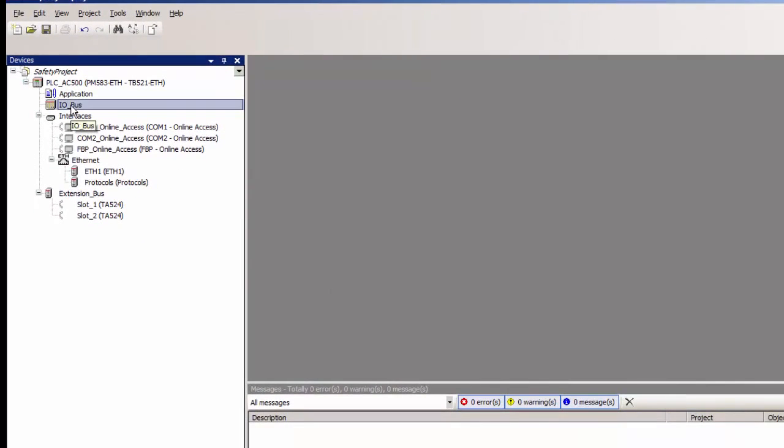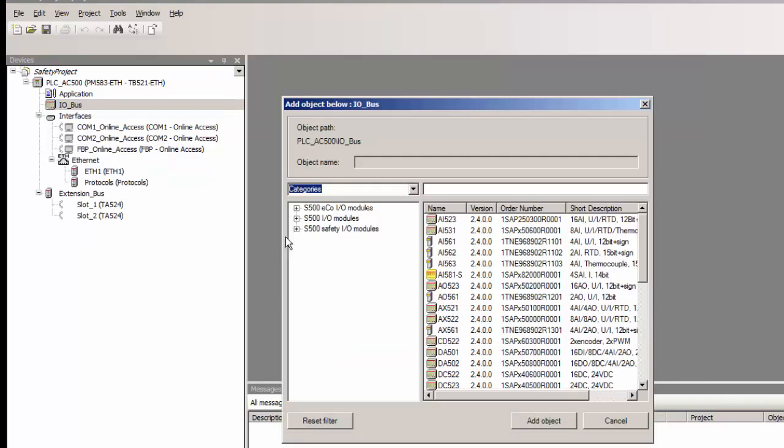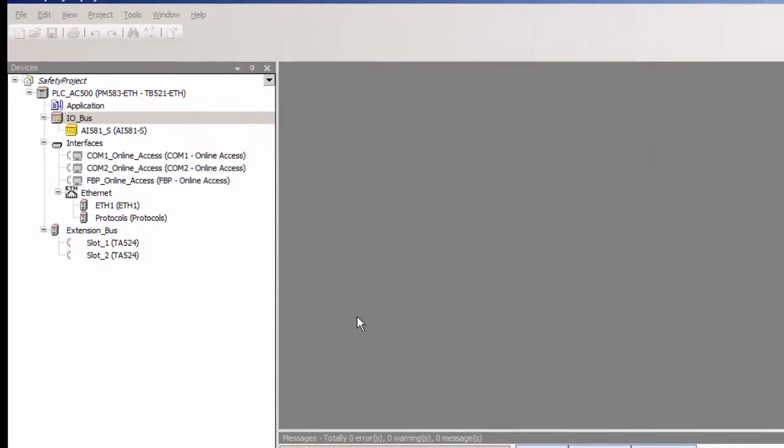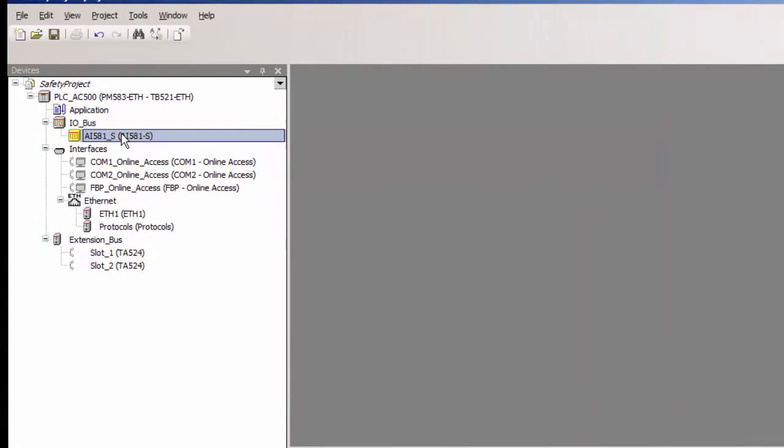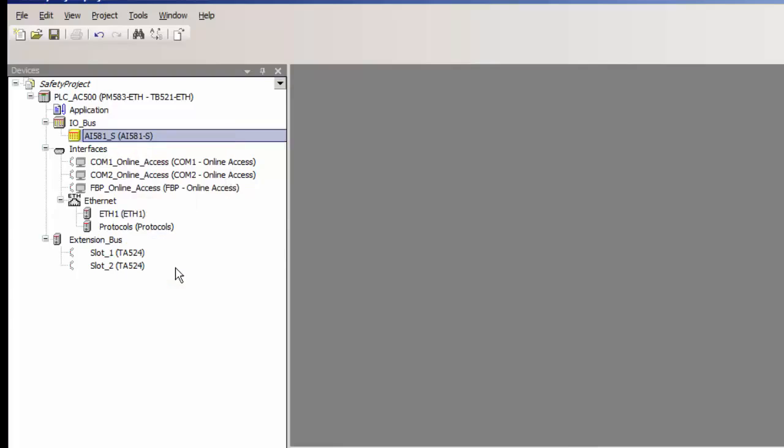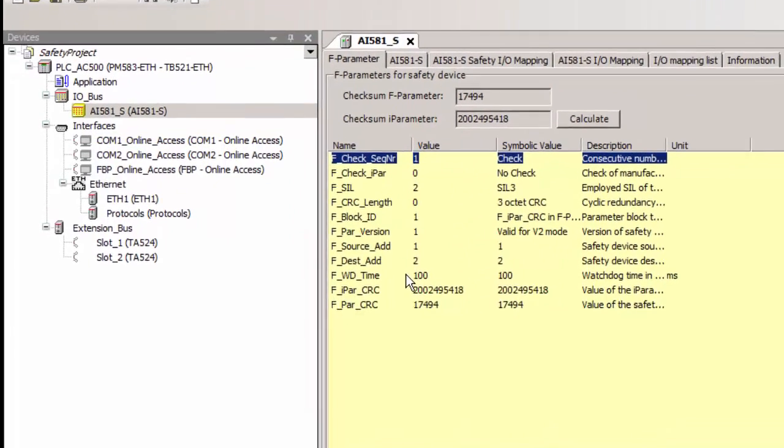Now we add the first safety module AI581S, which is an analog module on the I.O. bus. Each safety module needs to be set with the right failsafe parameters in order to ensure proper communication with the safety CPU. These settings influence the PROFIsafe communication performance between the safety CPU and the safety I.O. modules.